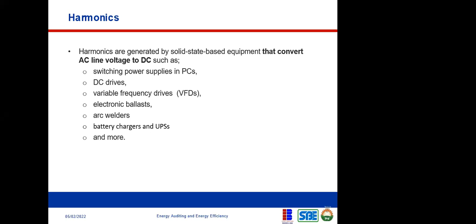There are DC drives. DC drive means, as the name implies, they use direct current. So when they're switching from alternating current to direct current, they induce harmonics into the power system. We have our variable frequency drives. All of these are systems that use direct current, but you're supplying an alternating current to them. So they have to convert that alternating current to direct current, and in the process of that conversion, they induce harmonics into the power system.